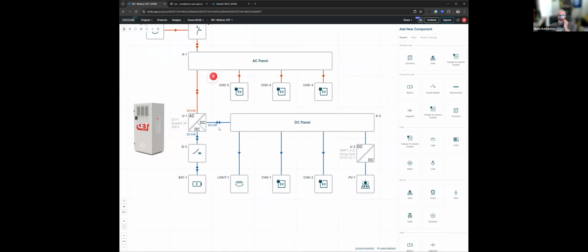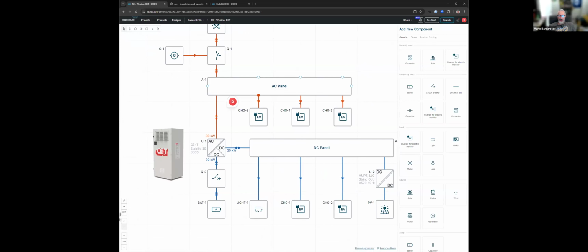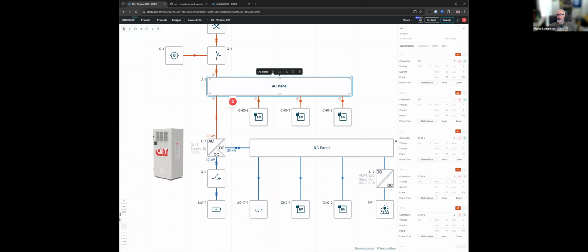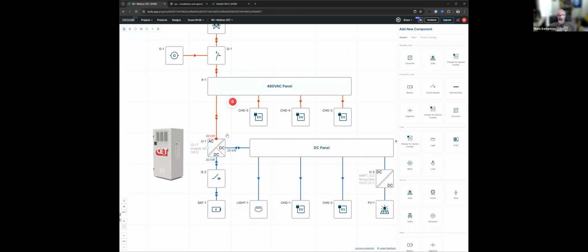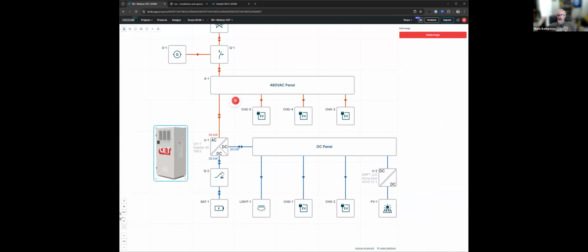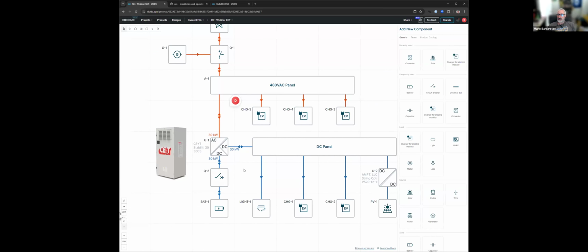By having galvanic isolation, you're isolating these issues to your EV chargers. You'll still have your battery and your connection to the AC. It's not going to shut down the entire unit. It makes the system very reliable and very robust. That's what galvanic isolation does for you. We can discuss short circuit, we can discuss safety, but for EV charging, that's a big benefit that adds to the reliability of the EV charging stations.